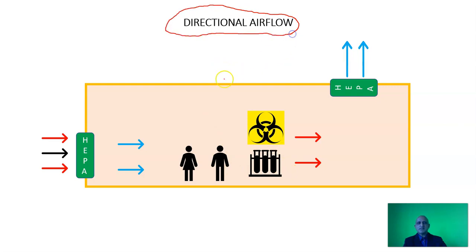A contained facility comprises a physical space in which the air pressure is maintained at negative with reference to the external environment. This ensures that air flows into the facility and when it exits, it flows out through a HEPA filter.